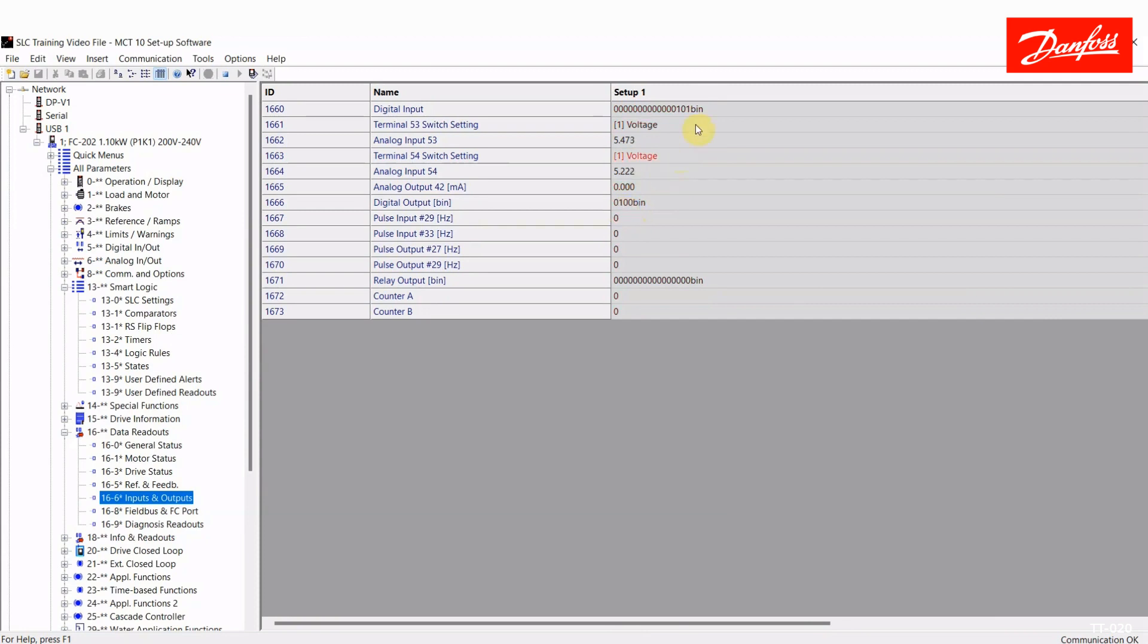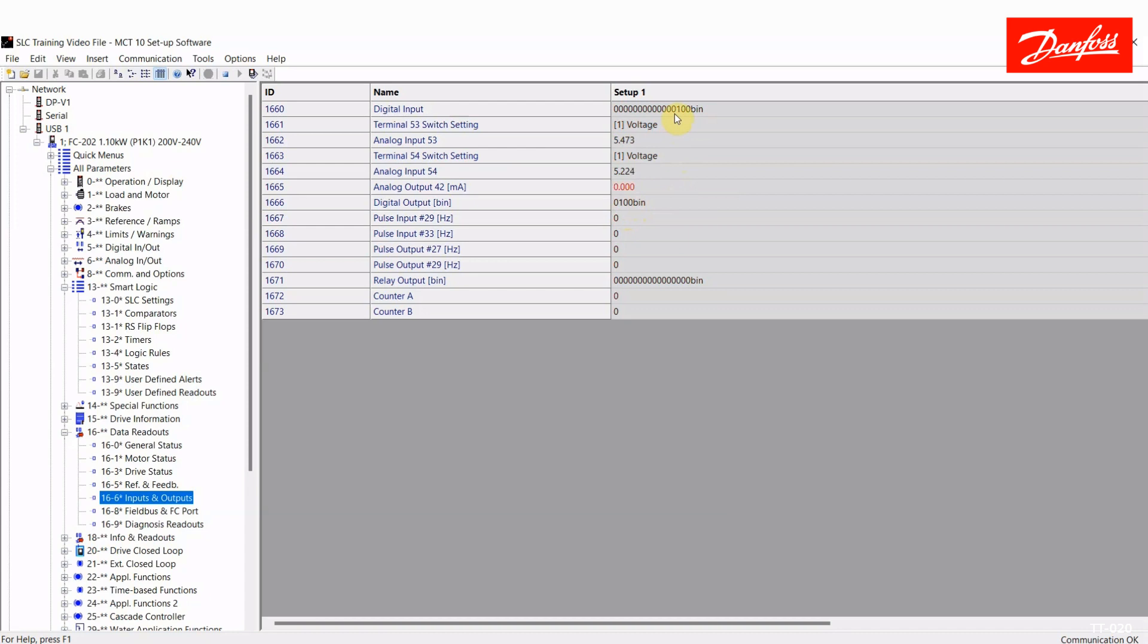Now I'm going to undo 33. So let's assume at that point the pump started, the water started pumping out of the tank and the high level switch opened like I show right now. You see that the flip flop remains set and it will remain set until the low switch is hit. So we'll do that right now. That's digital input 32. And we can see that the flip flop actually dropped out.